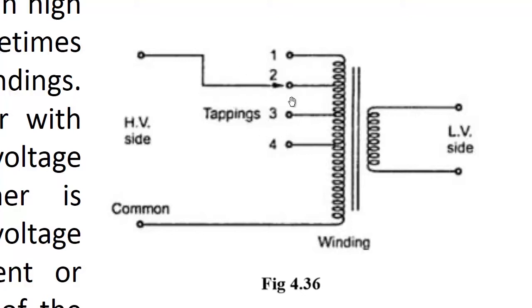So, by changing this, you can vary the number of turns associated with the primary. Once you connect the supply voltage to 4 and common, the number of turns associated with the primary will be minimum. Similarly, once you connect the supply to terminal 1 and common, the number of turns associated with the primary is maximum. So, there are 4 tappings, and the voltage associated with the primary can be changed by changing the tappings.